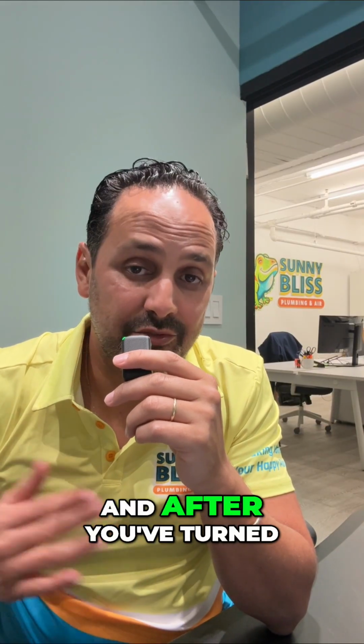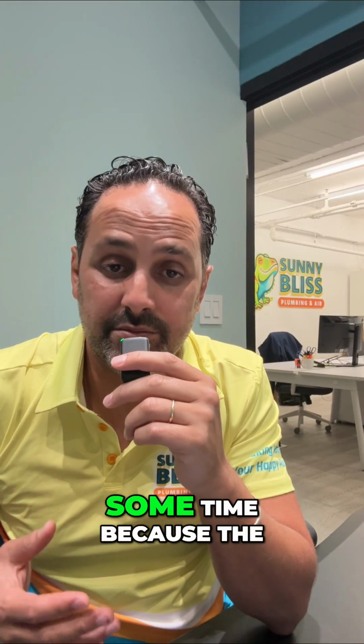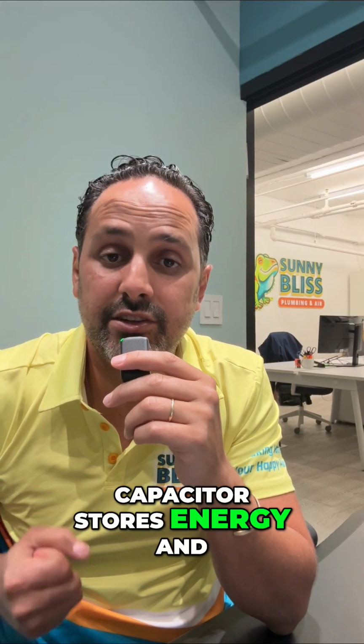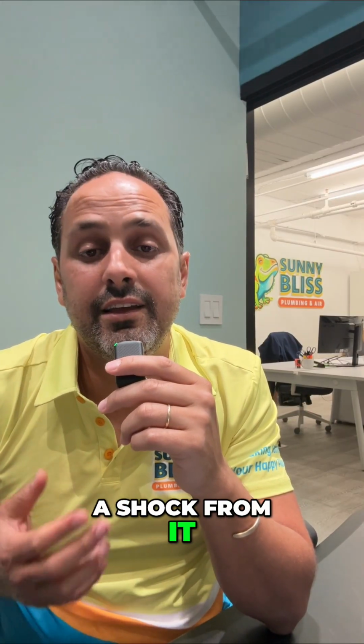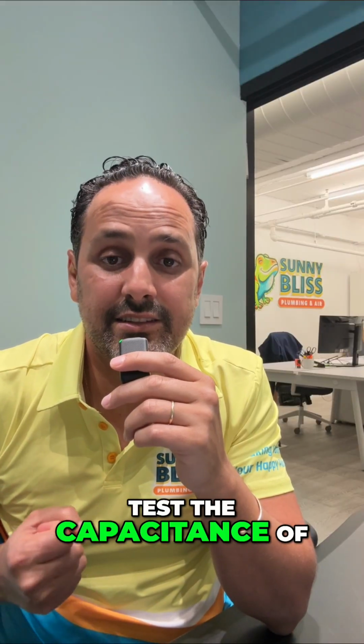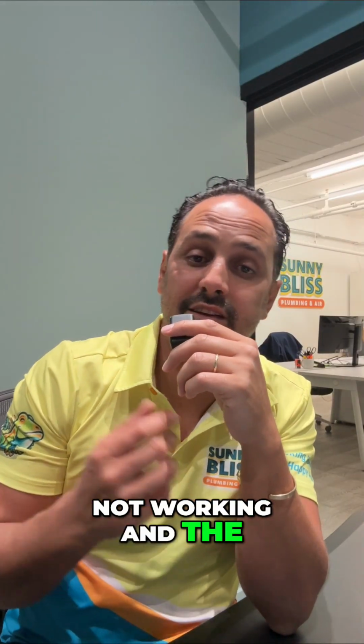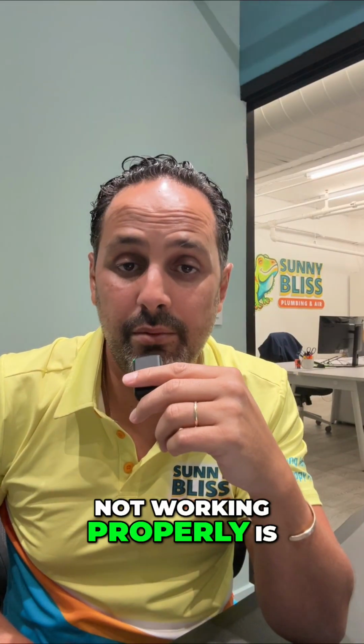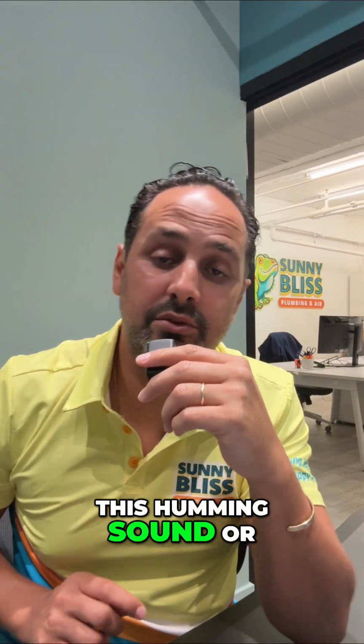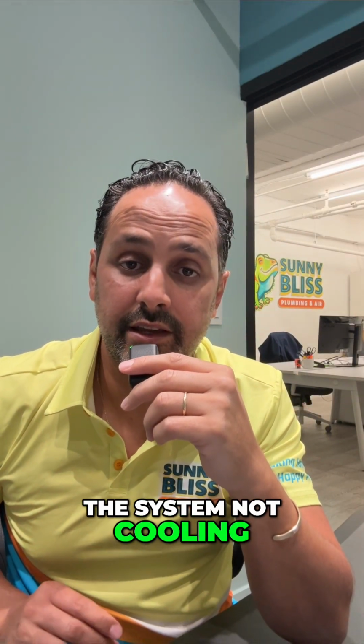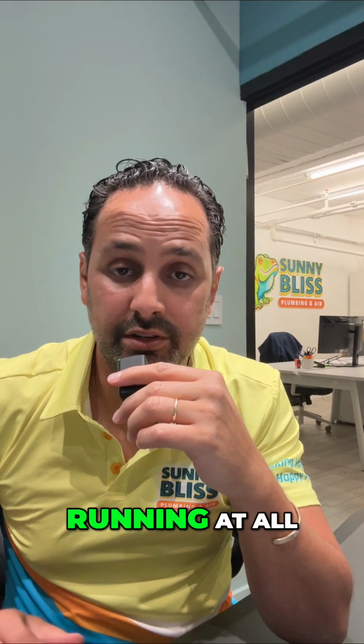But if you're handy and want to do it, make sure you turn off the power, and after that wait some time, because the capacitor stores energy and can still give you a shock. Then test the capacitance of the capacitor. Some of the symptoms of the AC not working due to a bad capacitor are a humming sound, the system not cooling even though it's running, or the system not running at all. I hope this was helpful.